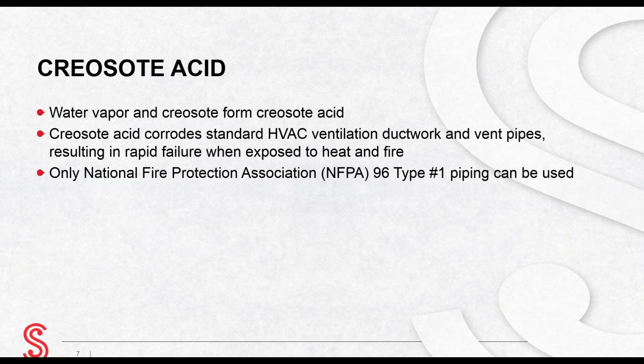Type 1 ducts are constructed of and supported by carbon steel not less than 0.06 inch in thickness, or stainless steel not less than 0.048 inch in thickness. They are liquid tight. They do not allow water vapor, grease vapor, or creosote vapor to leak outside the duct. Ductwork and vent piping that are not NFPA 96 Type 1 fail rapidly when they are exposed to heat and fire. This results in a rapid spread of fire and fire damage.